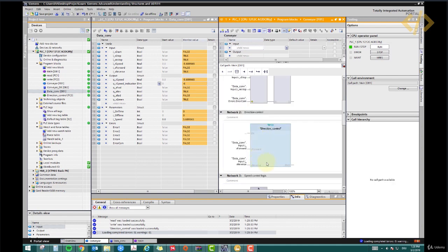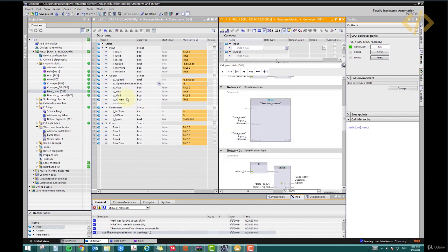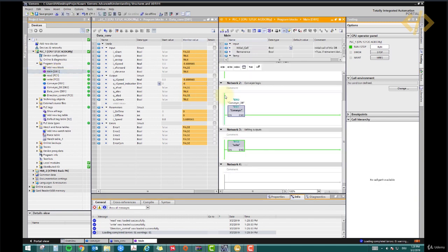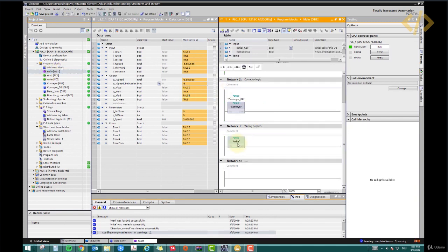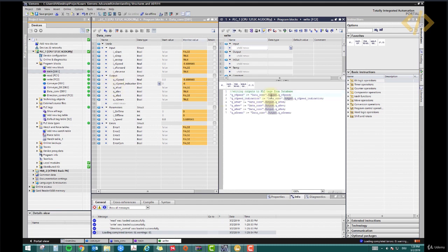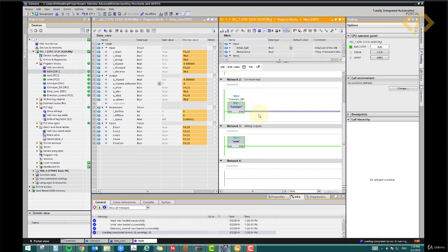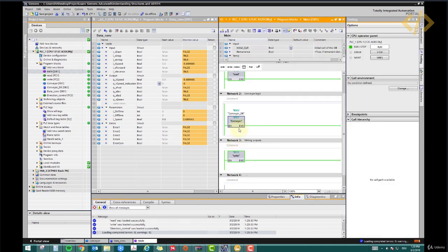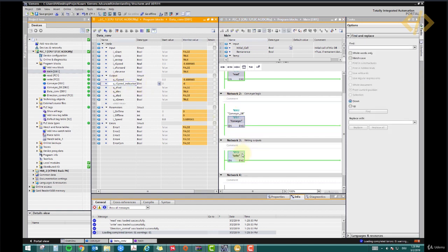All right. Now, what is happening next in the main logic? We are now writing the values. So whatever values we have written in the output in the data block are moving back to the PLC tag. The read function was reading from the PLC tag to the data block, and this FB solves the logic, moves the value into the data block, and then the output goes back to the PLC tag. So this is exactly what we have discussed before.